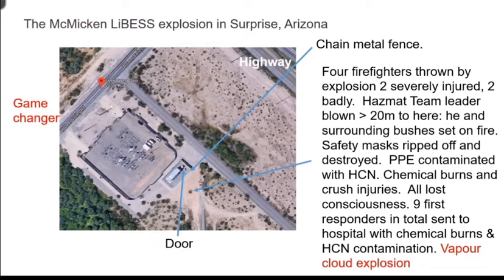1 hour after the smoke alarm triggered, at the remote monitoring station, the technician happened to glance at the monitor and realized there was a problem, drove to the site and met the fire service who just turned up. So this is an hour after that smoke alarm triggered. They waited a further 2 hours with the firefighters going online to try and understand what a lithium-ion battery was, what the risks and hazards were, before they opened the door.